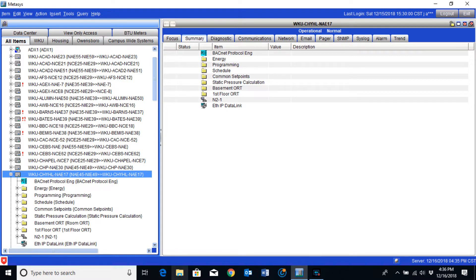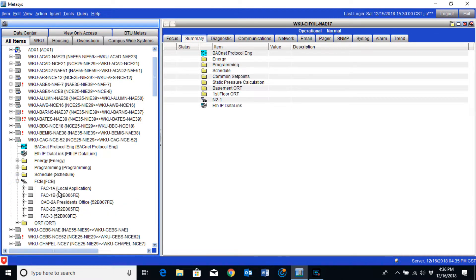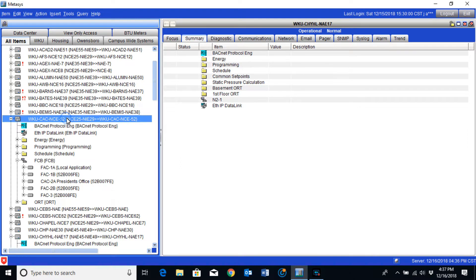NAEs are a communication go-between for the system to be able to talk to the individual controllers. An NCE is a Network Controller Engine. This device is actually going to have hardware points on the device itself. The difference between the NAE and the NCE is just that — an NCE can function as an NAE as well as a controller. Depending on the building and the system, it is basically a single device that does a dual function.